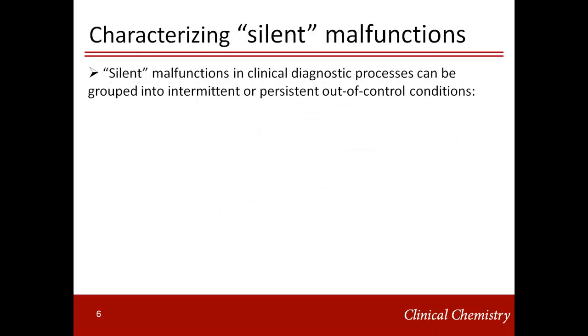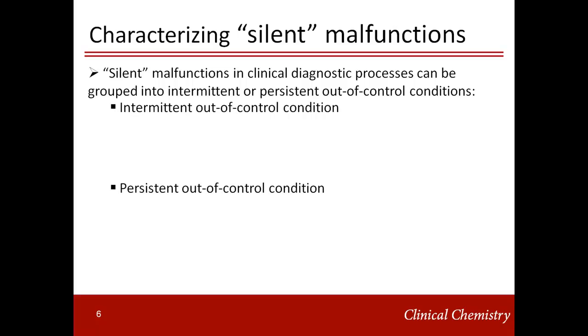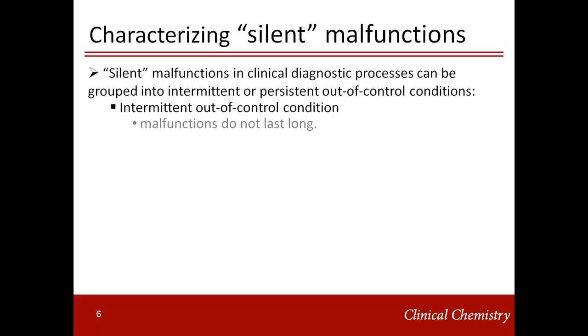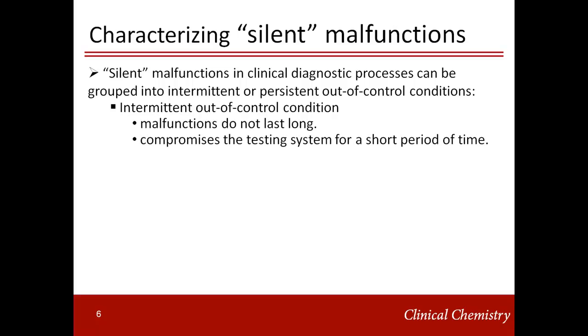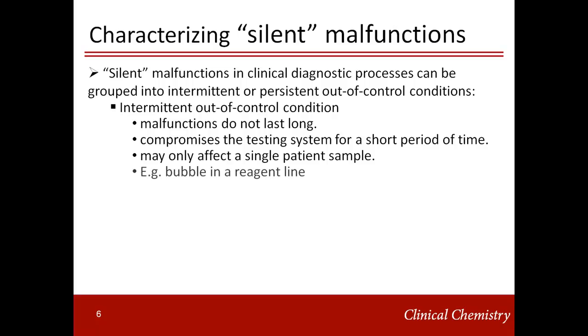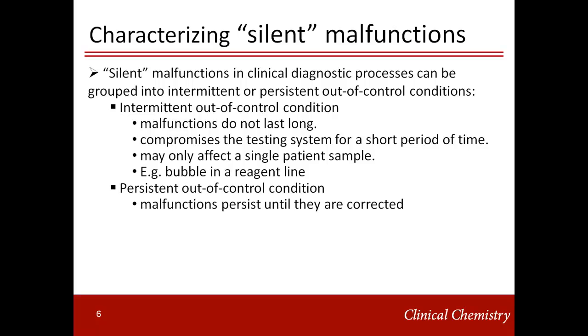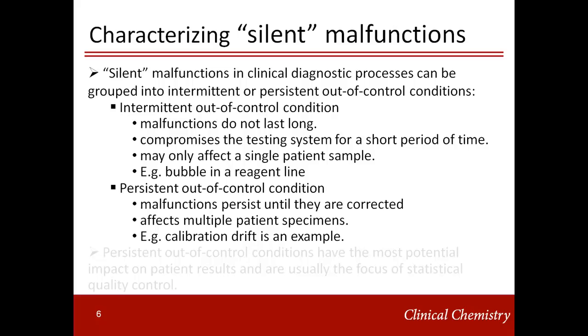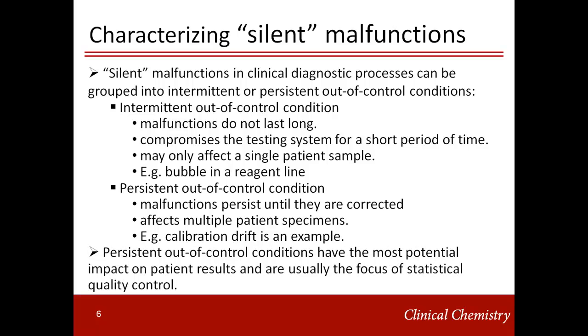Silent malfunctions can be grouped into intermittent or persistent out-of-control conditions. Intermittent out-of-control conditions do not last long — they compromise the testing system for a short period and may only affect a single patient result. An example is a bubble in a reagent line. Procedures such as delta checks, discordant checks, and many built-in instrument checks are designed to detect these, but intermittent out-of-control conditions are not the focus of this series. Persistent out-of-control conditions persist until corrected and affect multiple patient specimens — calibration drift is an example. These persistent conditions are usually the focus of statistical quality control.